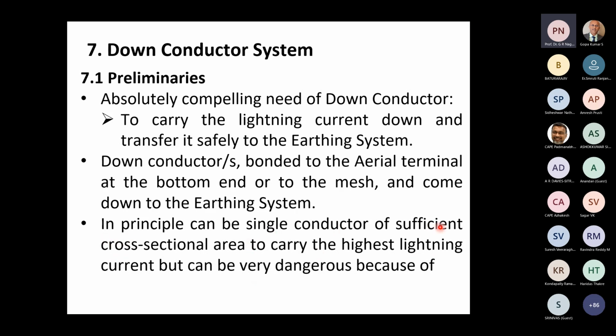Single conductor can also be used. But remember, we have discussed the dangers of a single tall conductor in the second webinar. The contact potentials will be huge, hundreds of kilovolts. The ground potentials can be huge, tens or even hundreds of kilovolts. Therefore, the current that can enter a person who is in the proximity can go from right up to 1000 kiloamperes to hundreds of amperes. So it can be extremely dangerous. So a single down conductor is a no.